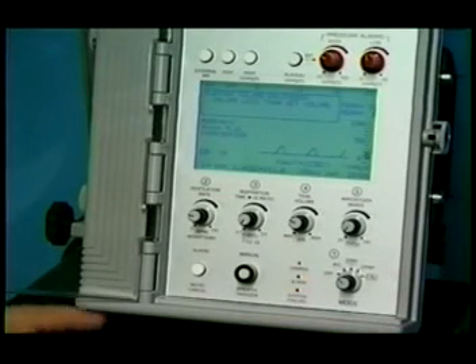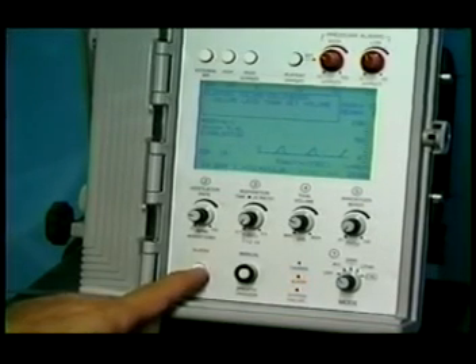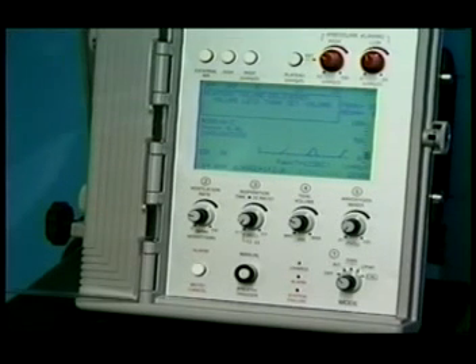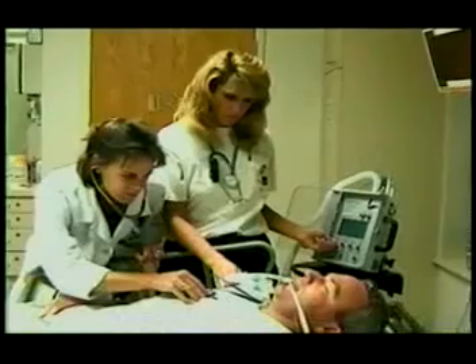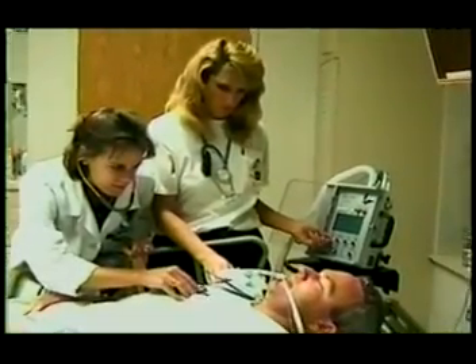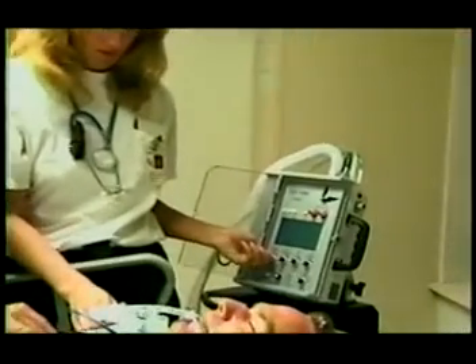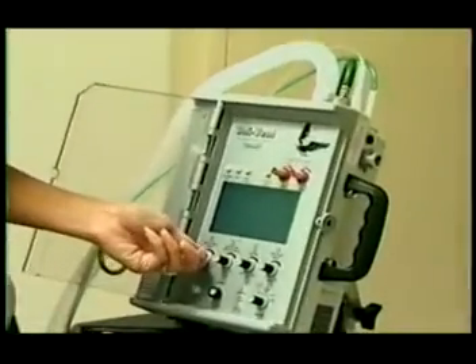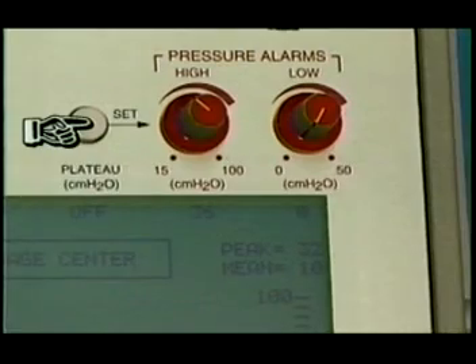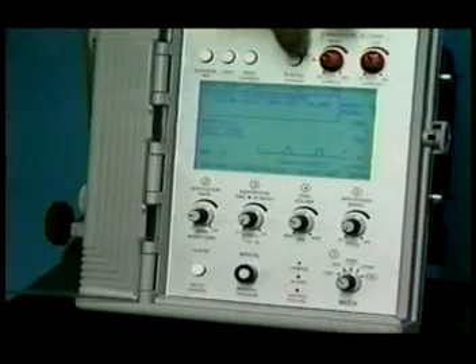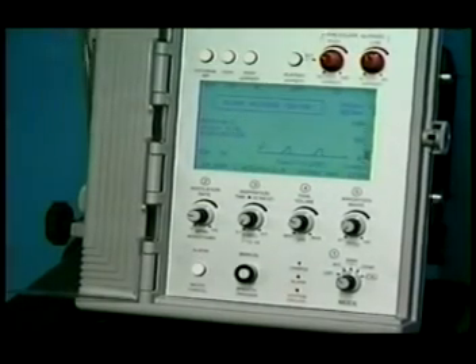Pressing the alarm mute cancel push button cancels the audible plateau volume advisory alarm, turns the alarm LED off, but allows the alarm message to remain so that anybody who looks at the screen will know that the ventilator is delivering less volume than it was set to deliver. We can cancel pressure plateau by pressing the push button to off. This cancels the remaining advisory message and returns us to our normal pressure waveform.